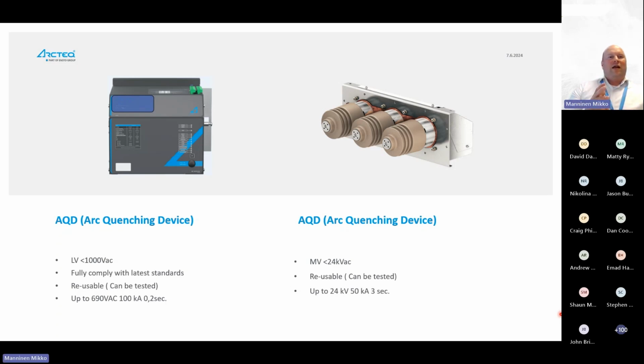As long as the main breaker, maybe the tie breaker, and the upstream breaker if necessary, they all open. Let's say the breakers which are surrounding the fault. So the arc quenching device's main task is to act fast, typically less than 5 milliseconds, and it can be even 3 milliseconds. So now if you consider, for example, 400 milliseconds trip time or 4 milliseconds total clearing time, of course it is a significant difference in the arc incident energy.